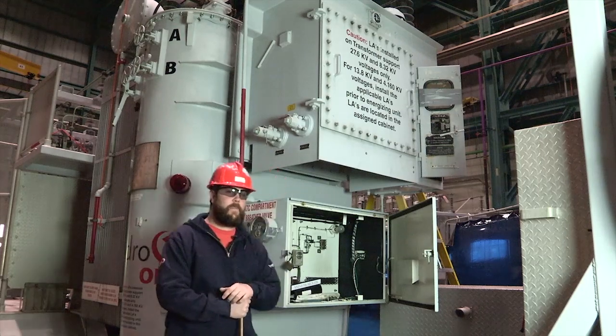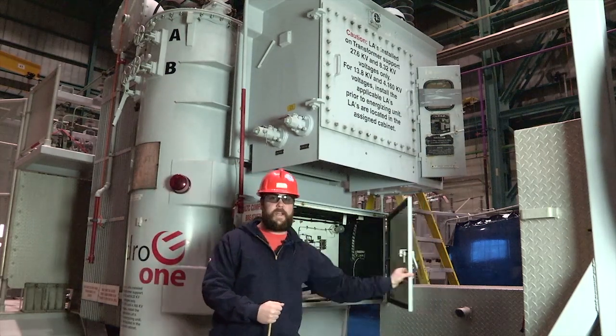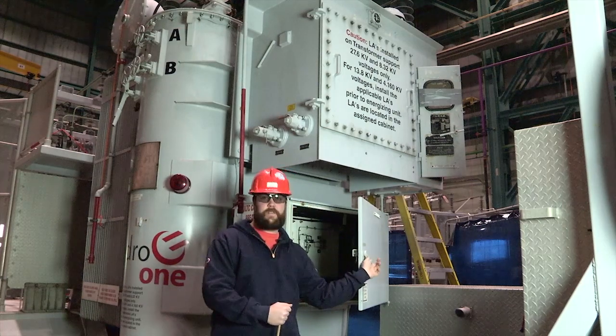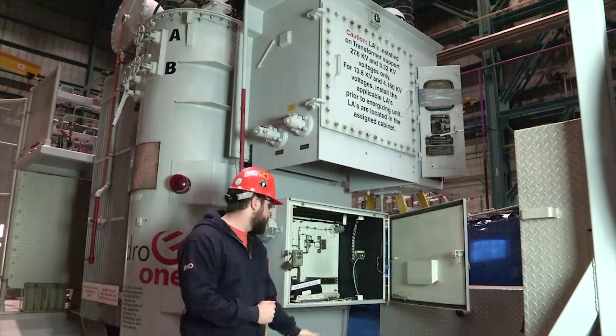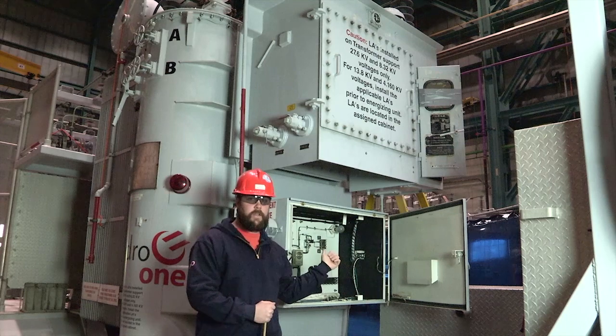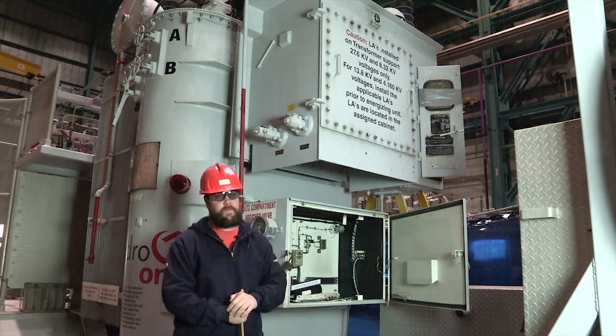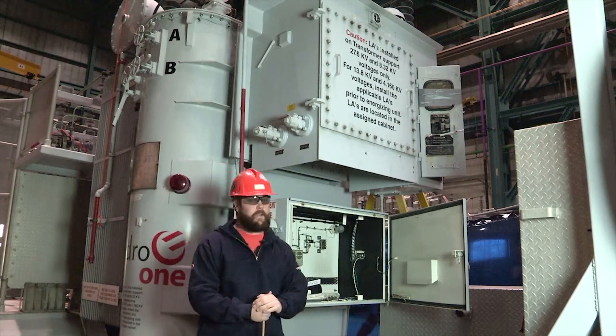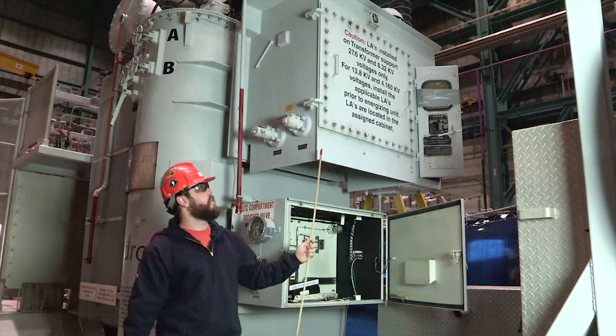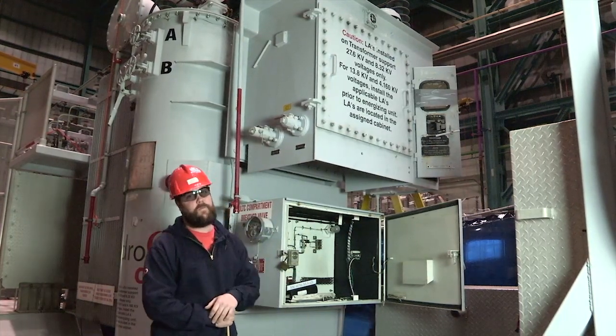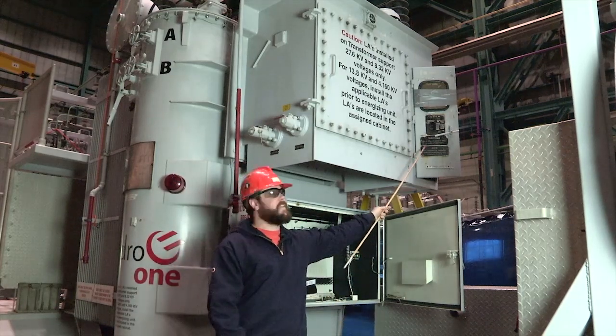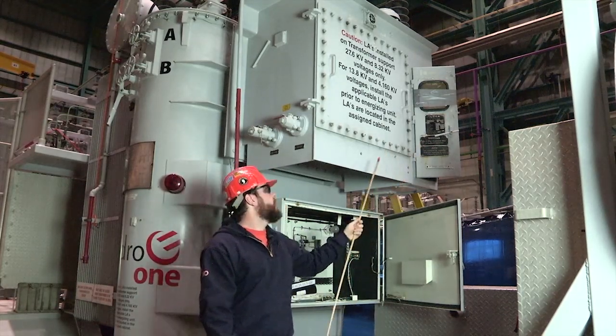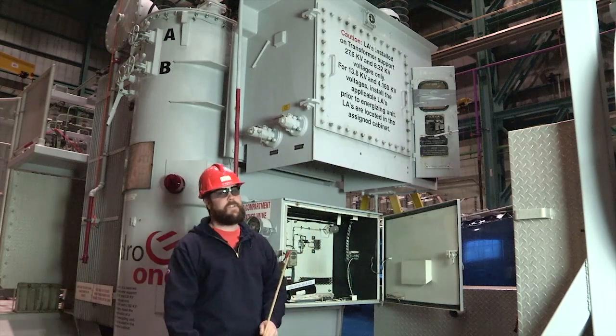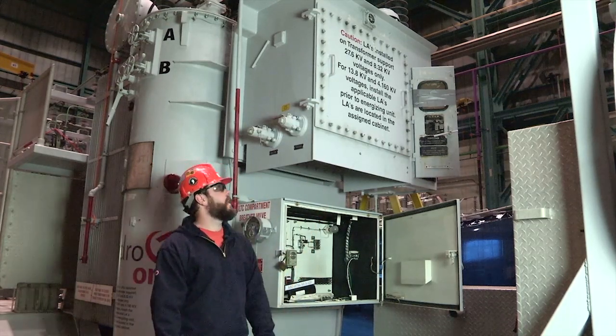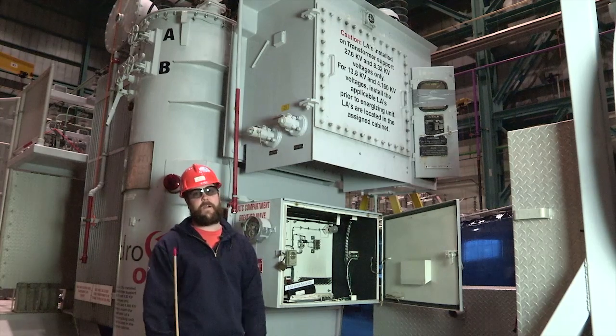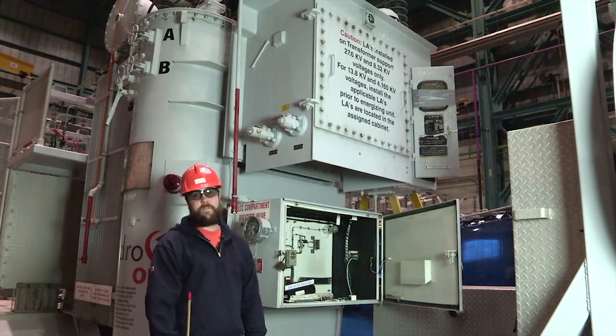Next, we're going to look at the mech box. We're just going to make sure that first off, the door gaskets, everything's fine, all hinges are greased, lubed, that's what you're going to want to do. You're going to look inside, make sure all breakers, light bulbs, heaters, everything's working, just routine maintenance we always do. Every year too, we have to do an SI on the ULTC if there's one. We just got to make sure that the nameplate's legible, everything's good and accurate. Make sure there's no leaks or a new gasket once you do the SI, and your drain valves, you want to go ahead and make sure that nothing's leaking on them, repair them if they are, and just give a once over on everything.